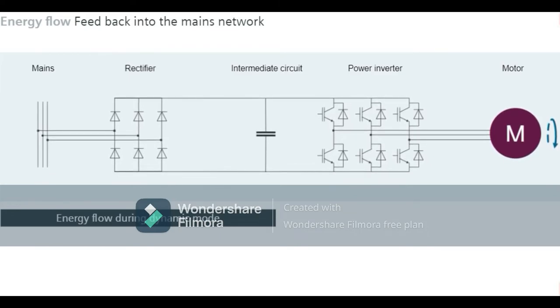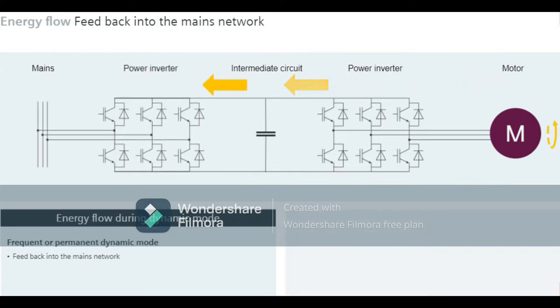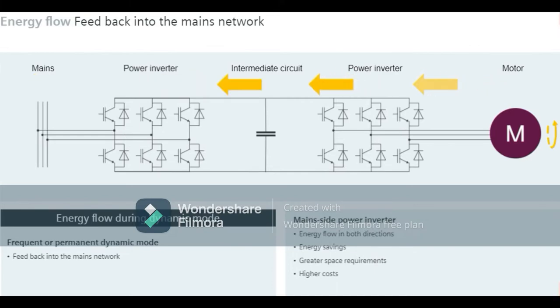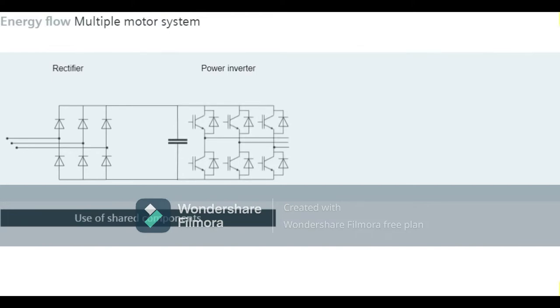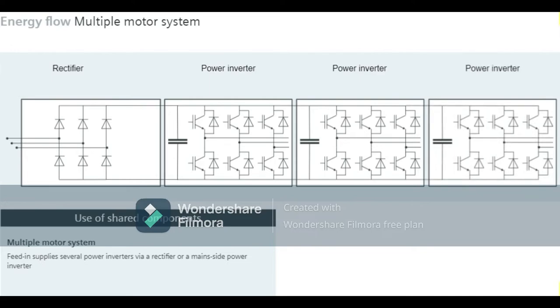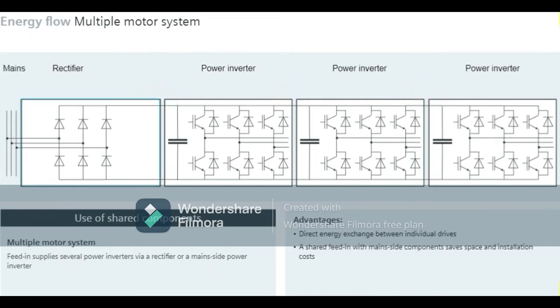If dynamic mode occurs frequently or permanently, a feedback into the mains network is a better solution. A mains-side power inverter allows the energy to flow in both directions, saving energy because the energy fed back into the network is provided to other electrical loads. The mains-side power inverter is the same as a motor-side power inverter in terms of size and structure, however this system has greater space requirements and entails higher costs. A multiple motor system refers to a layout where a feed-in supplies a number of power inverters via shared mains-side components, enabling direct energy exchange between individual drives, shared installation cost savings, and shared use of a brake resistor or mains-side power inverter.